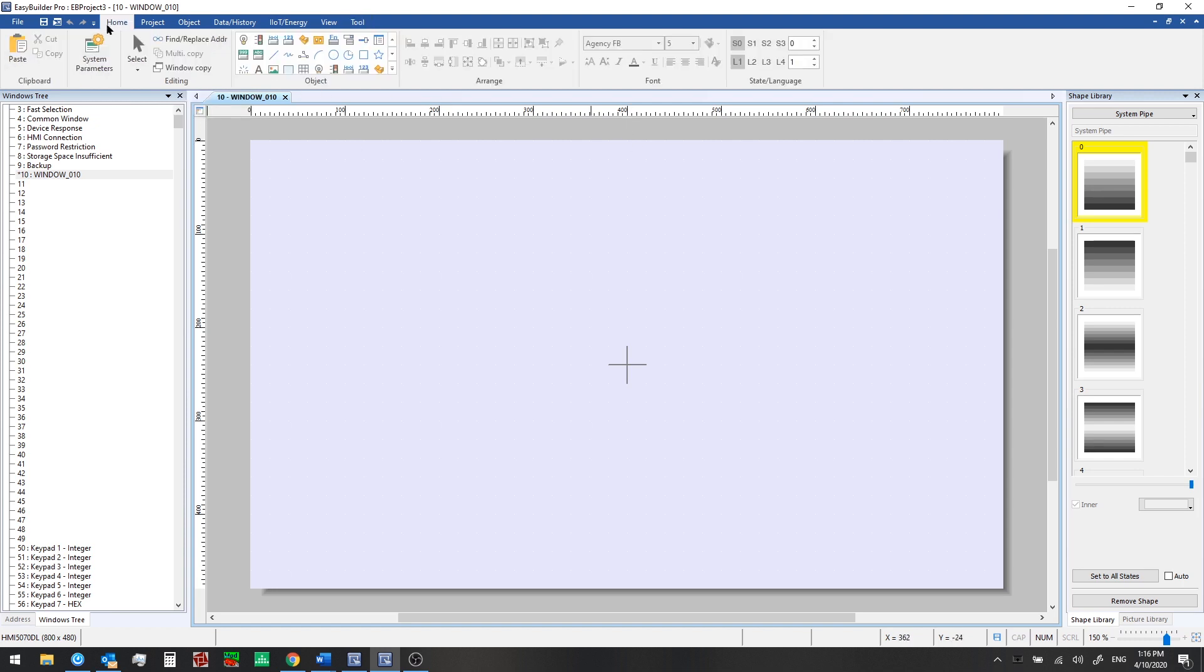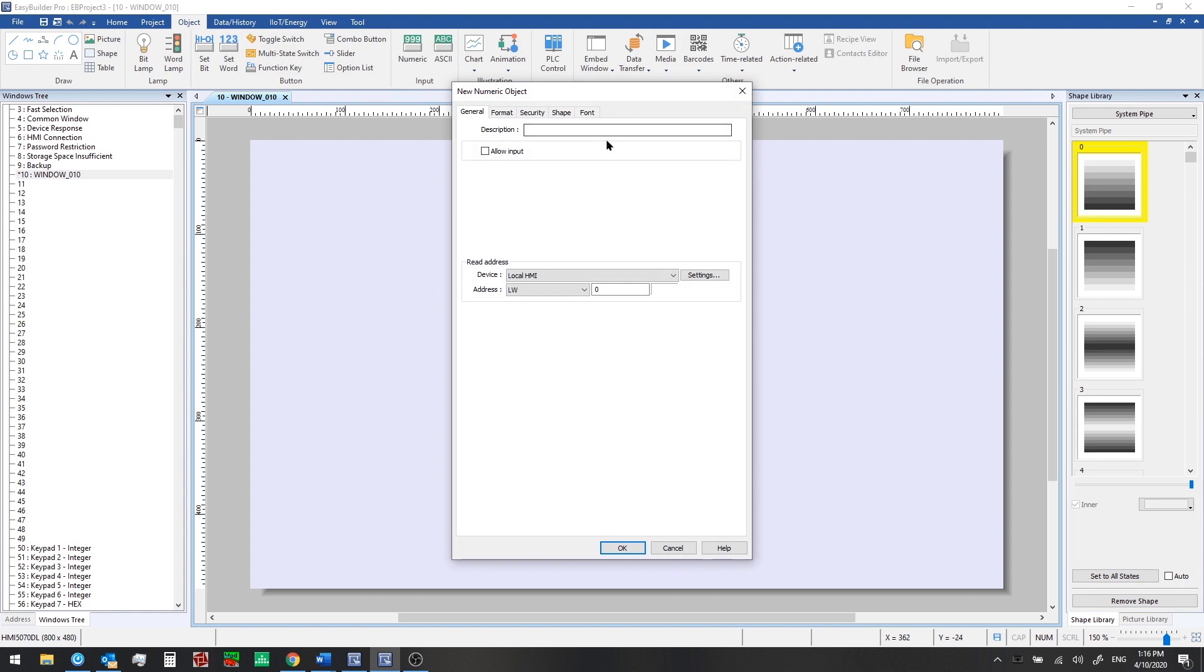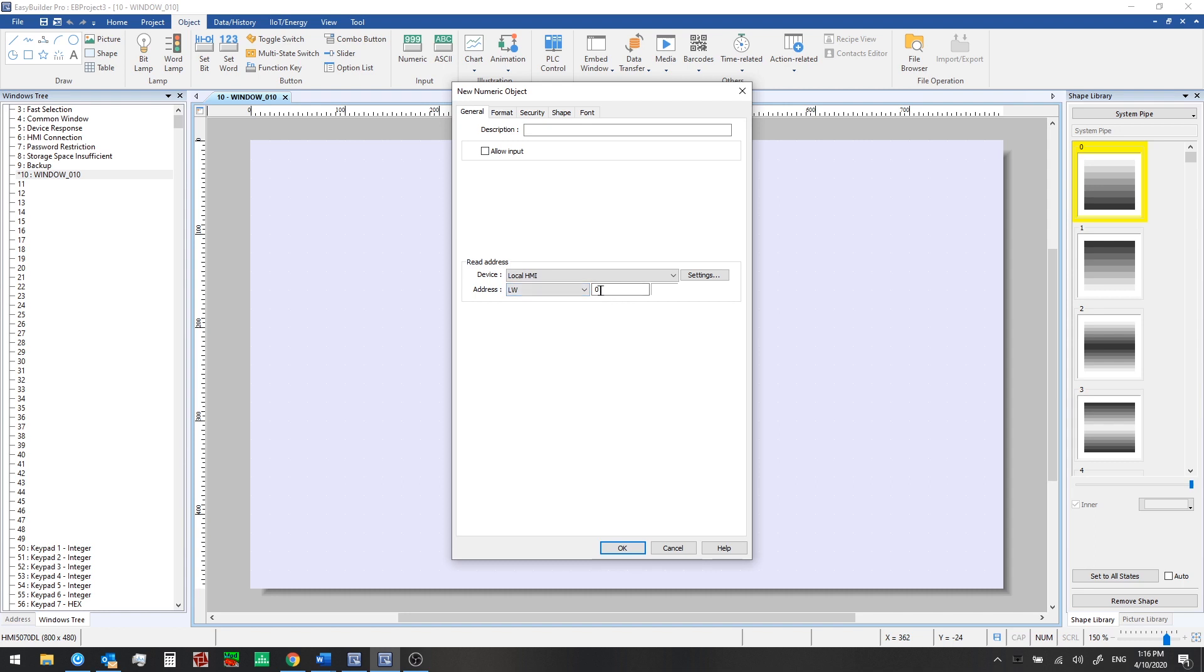For now, we'll go back and we'll start by adding a numeric display to our window first. So go to the object tab for this and select numeric. And this new numeric object window pops up. Here we can select a read address. Local word would be the default. So this is register based memory in the HMI. And we can enter an address here. So local word zero would be the first register that we can read data from using this numeric display.